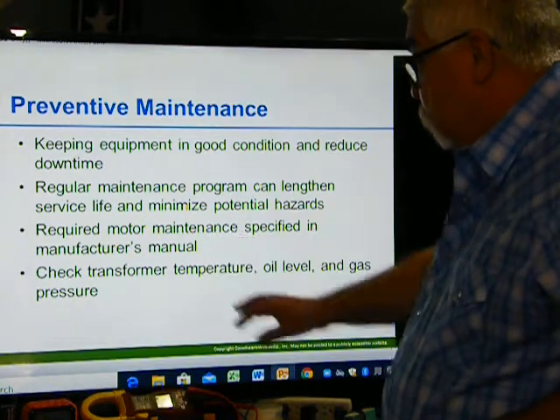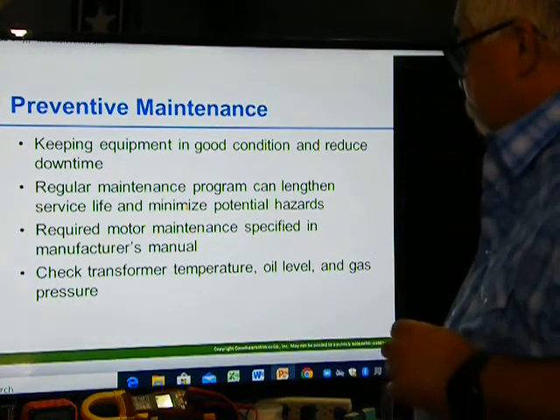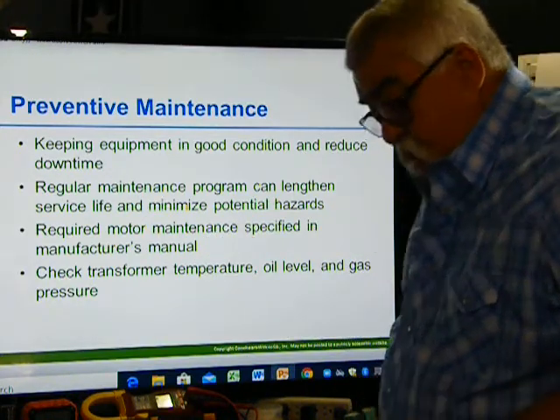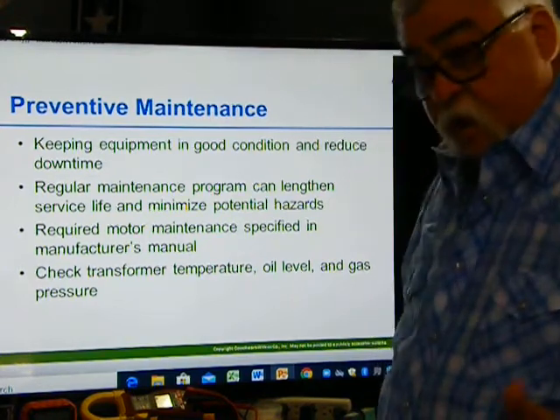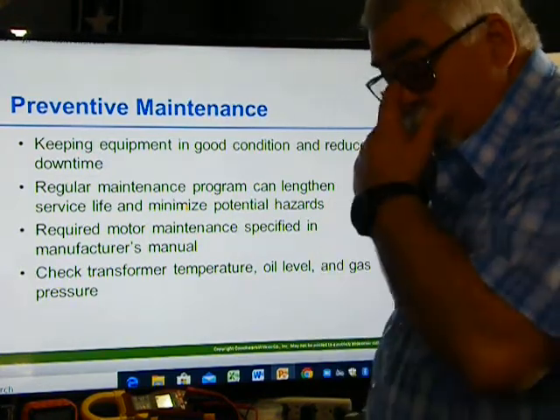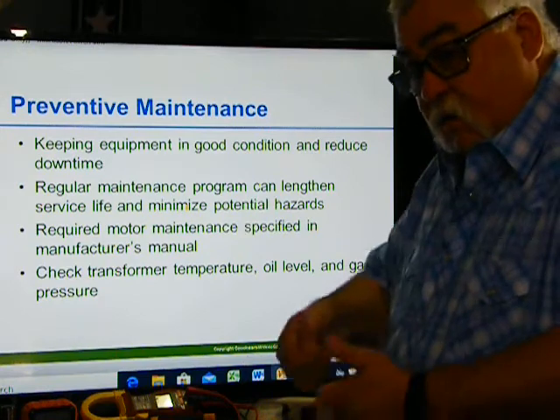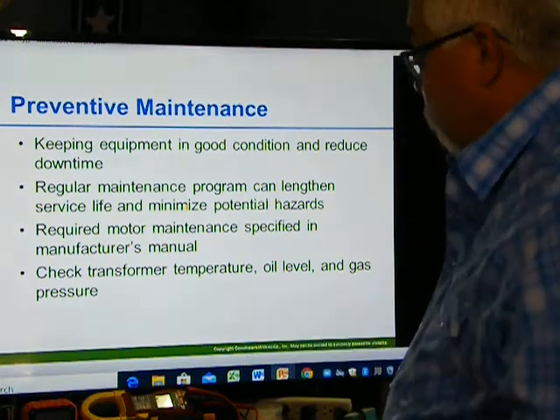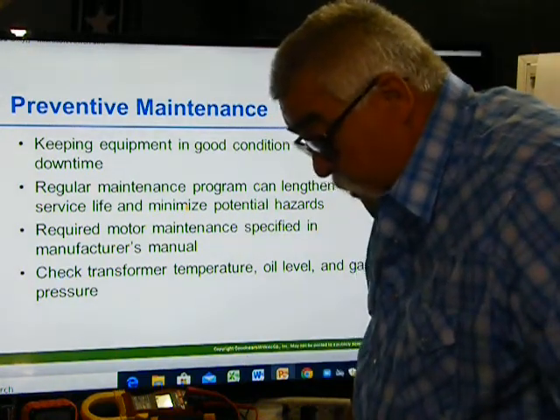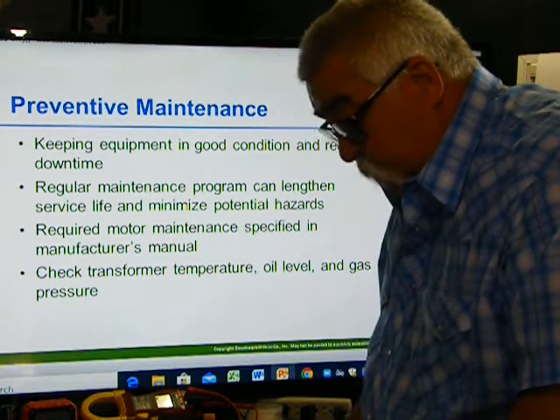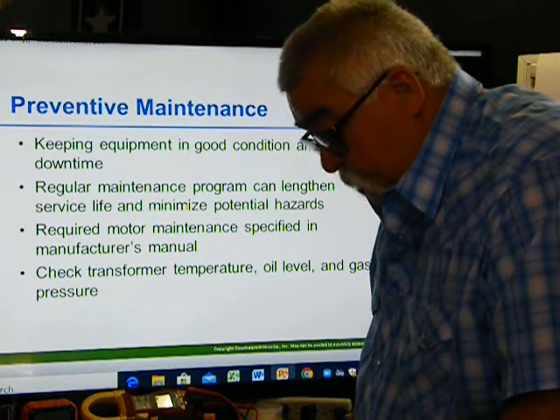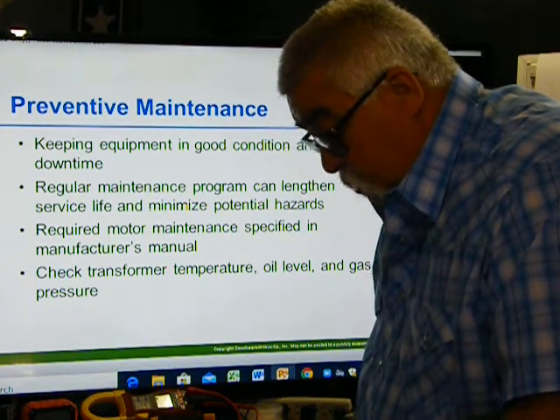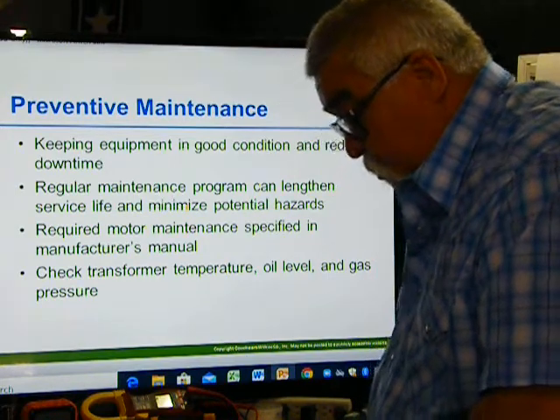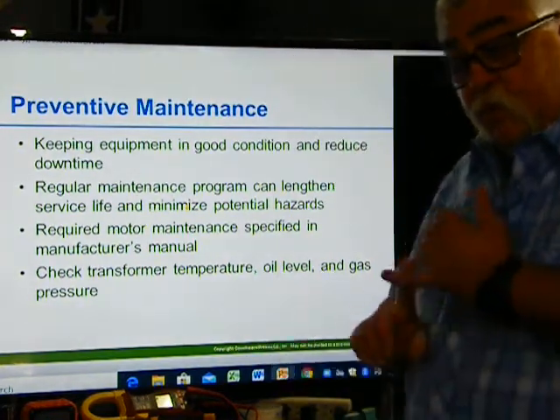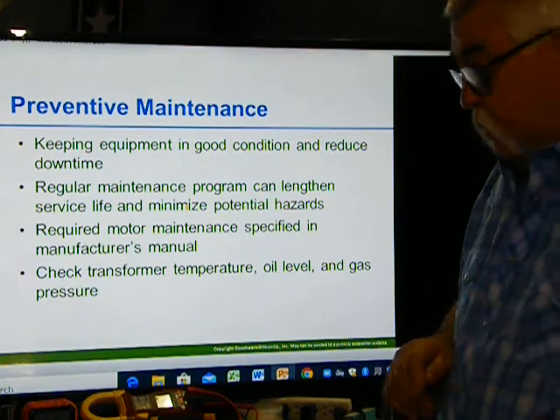Where it's talking about the required motor maintenance specified by the manufacturer's manual. So, your lubrication: one of the questions yesterday was that one thing you have to take caution with is getting too much grease on. Bearing problems may be caused by excessive loading, poor lubrication, or installation of the improper type of bearings. Okay, so we have to make sure we use the right size bearings and keep them lubed.